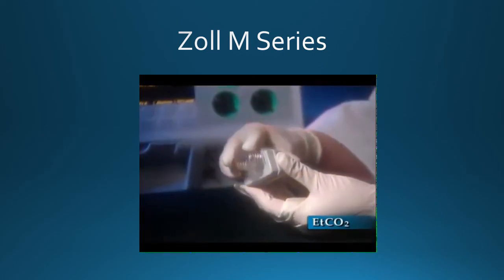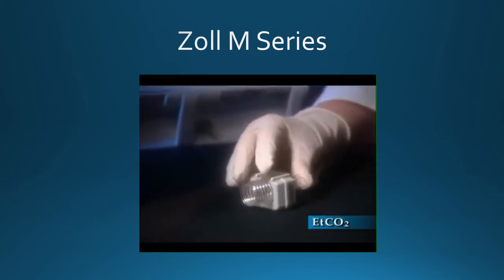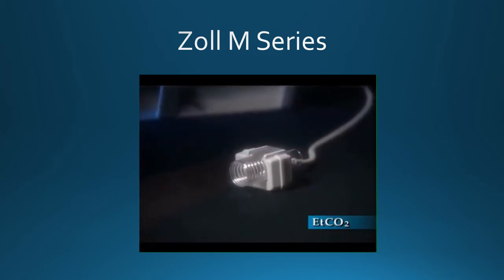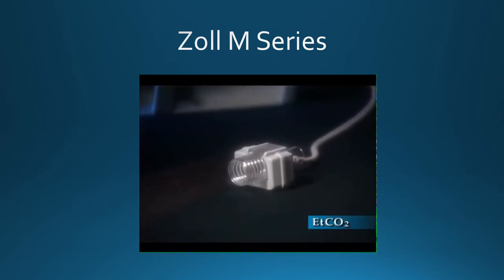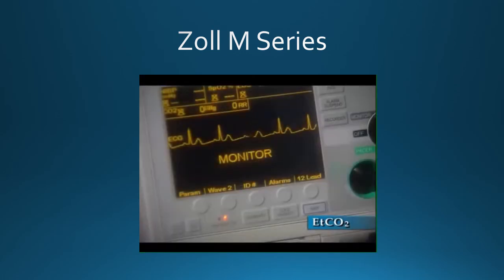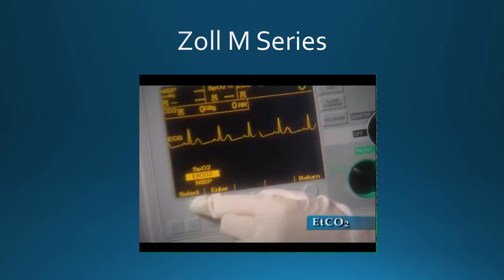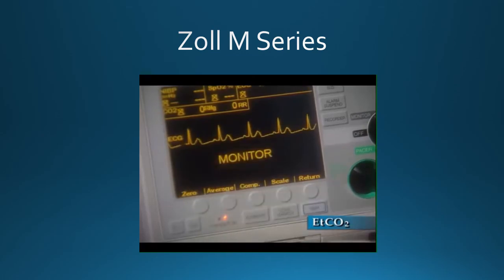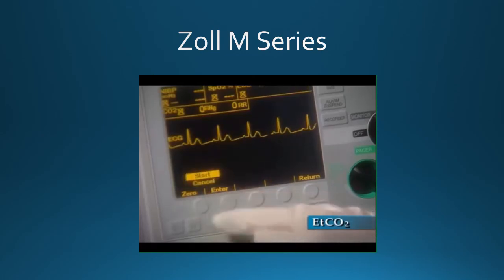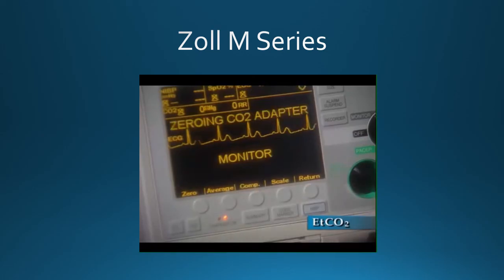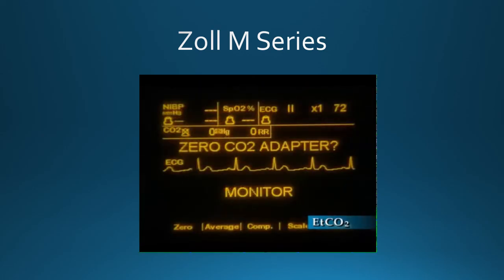Attach the airway adapter to the capnostat. The first time a given adapter type is attached to the capnostat, it must be zeroed. To zero the adapter, press the parameter soft key. Select the EtCO2 menu item, then press Enter. Press the zero soft key. Select Start using the zero soft key, then press Enter. Zeroing CO2 adapter will be displayed for about 15 seconds.